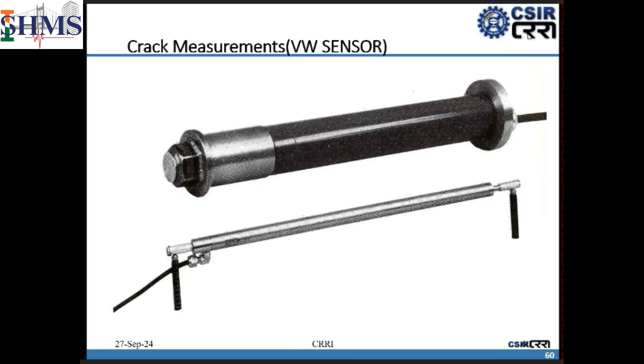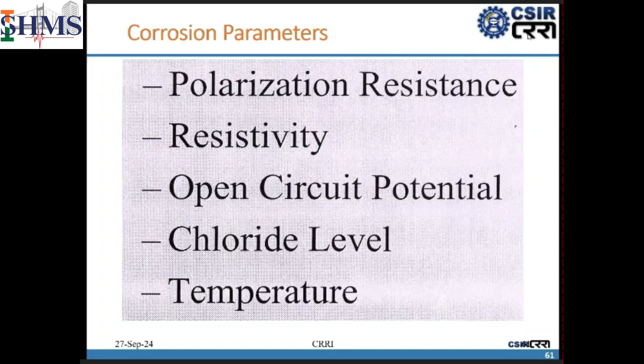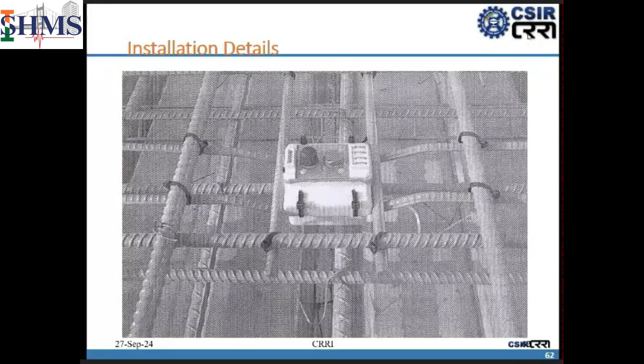Corrosion is one of the performance parameters, with different techniques like polarization resistance, resistivity, and open circuit potentials. There's also indirect measurement of corrosion through chloride level measurement, supplemented by temperature measurement. This sensor is fixed inside the body before concreting and works on polarization resistance, with this being the junction box for that sensor.